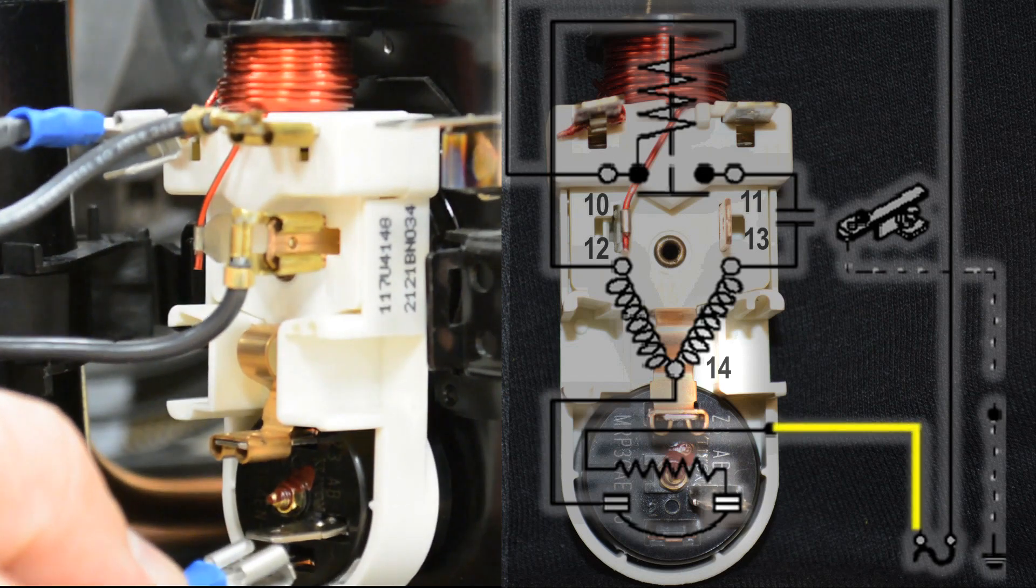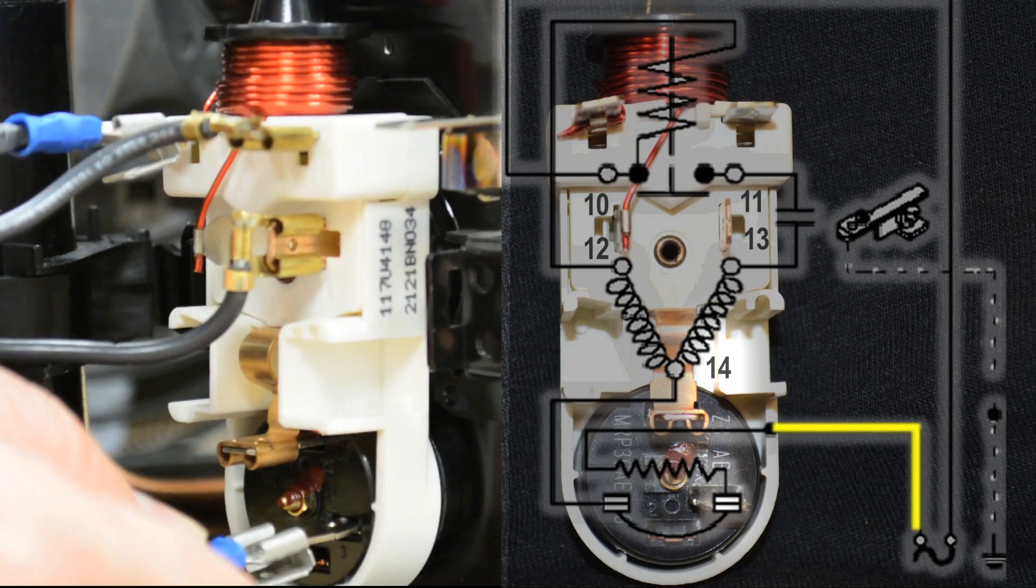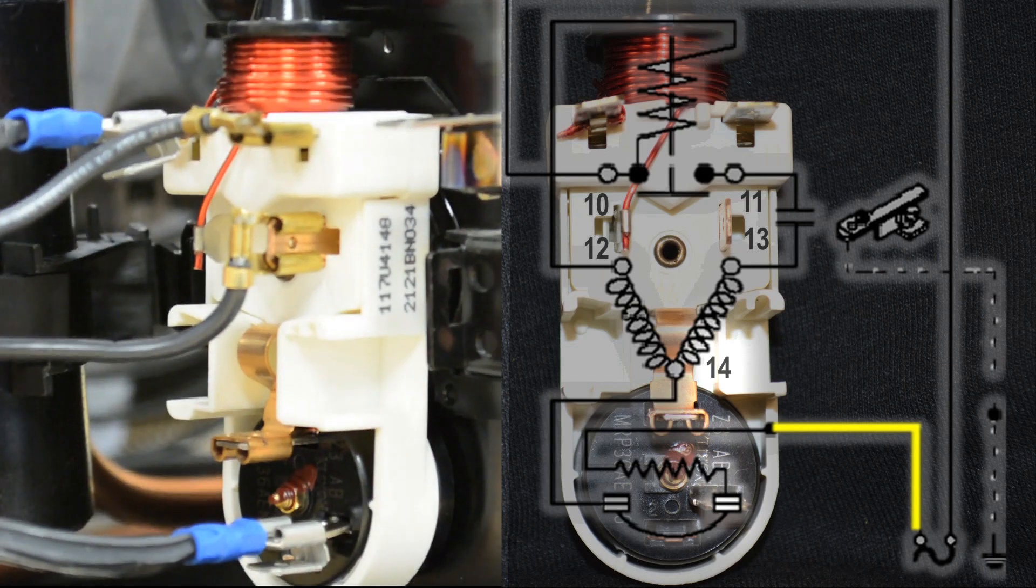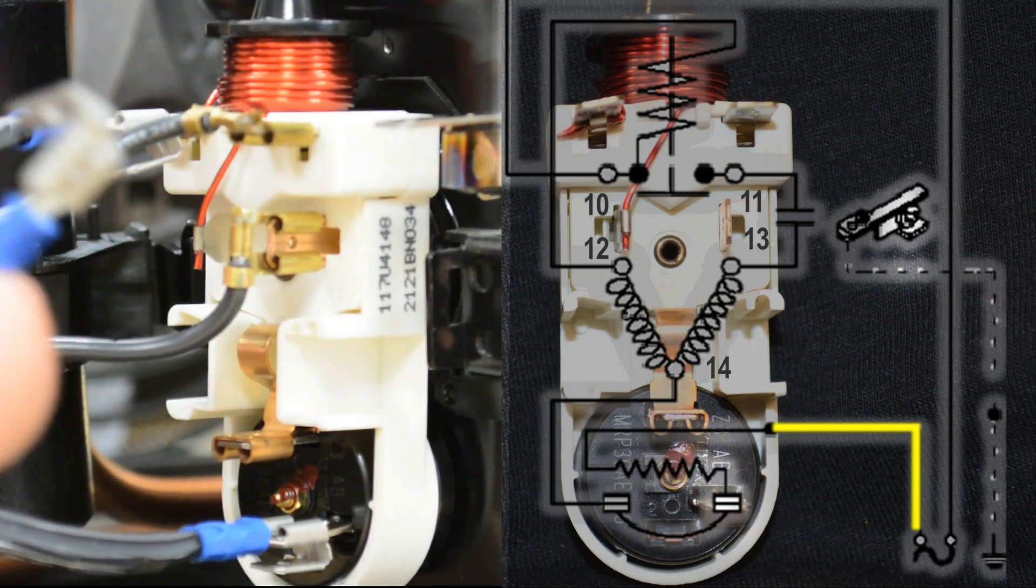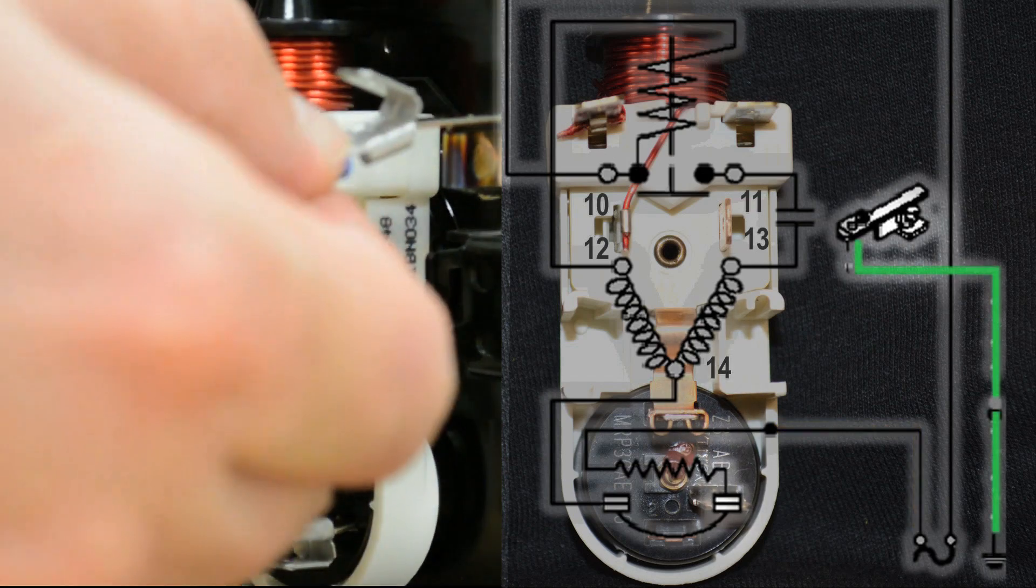Next we'll connect neutral to the compressor motor protector through number 14 on the start relay. Don't forget to connect the ground wire to the ground terminal on the compressor shell.